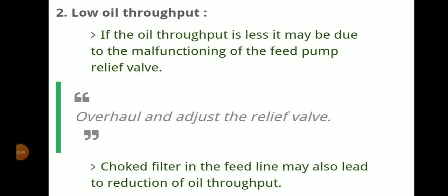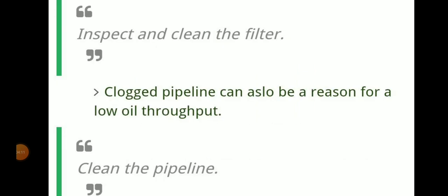A choked filter in the feed line may also lead to reduction of oil throughput. So we need to inspect and clean the filter.